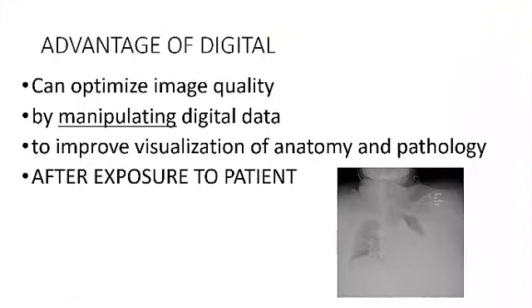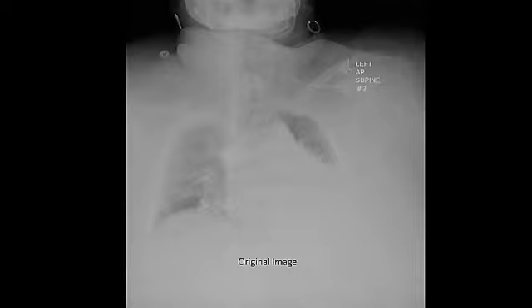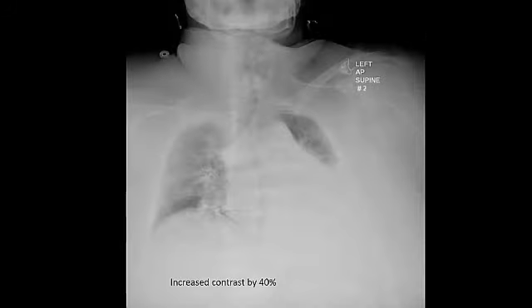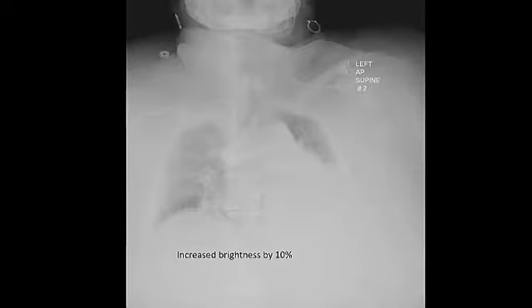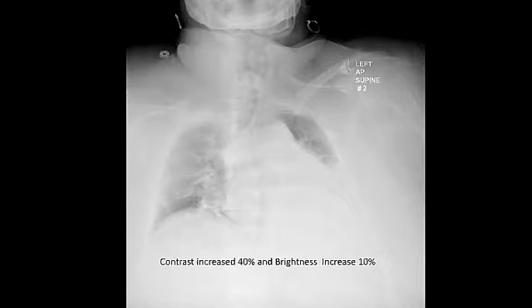The advantage of digital acquisition of information for X-ray today is much different than film screen acquisition of the past. With digital, we can optimize image quality by manipulating the digital data to improve the visualization of anatomy and pathology after exposure to the patient. Let's take a look and see if we can improve the exposure of this original image. In digital, we can manipulate the dynamic range of the image by using contrast and brightness adjustments. Here we've increased the contrast by 40%. We again take our original image and just increase the brightness, and here we've increased the brightness by 10%. By manipulating the contrast and brightness, we can get a better diagnostic image than the original.